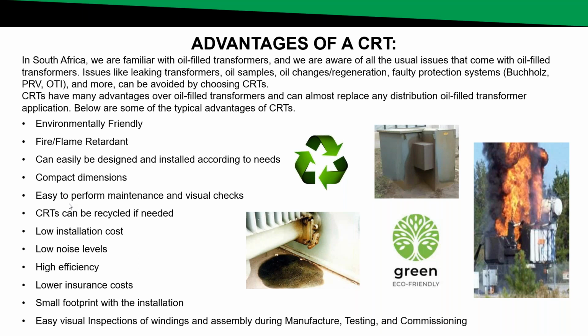Cast resin transformers also have a smaller footprint. If you think of an oil transformer, again, you need a bund wall around the oil transformer. You need cable boxes. You need conservators. You need radiators. All of these items on oil transformers take space. Cast resin transformers don't need any of the before-mentioned, and thus have a smaller installation footprint.